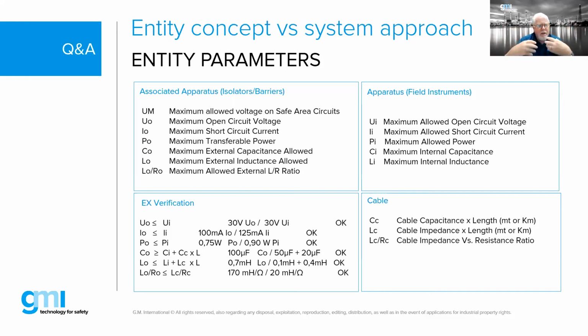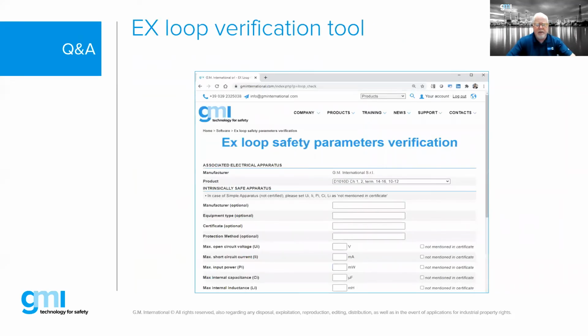Now in the U.S., historically we had not used IS as much as other people around the world had, and you would usually find a control drawing put out by the manufacturer of the field device. In the control drawing, it would specify: use this device because we've already checked the entity parameters. But in the real world, there's no reason why you cannot make that selection yourself.